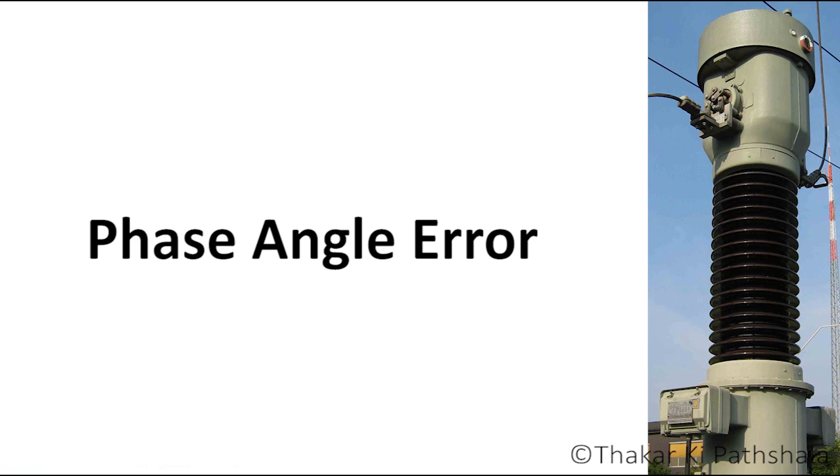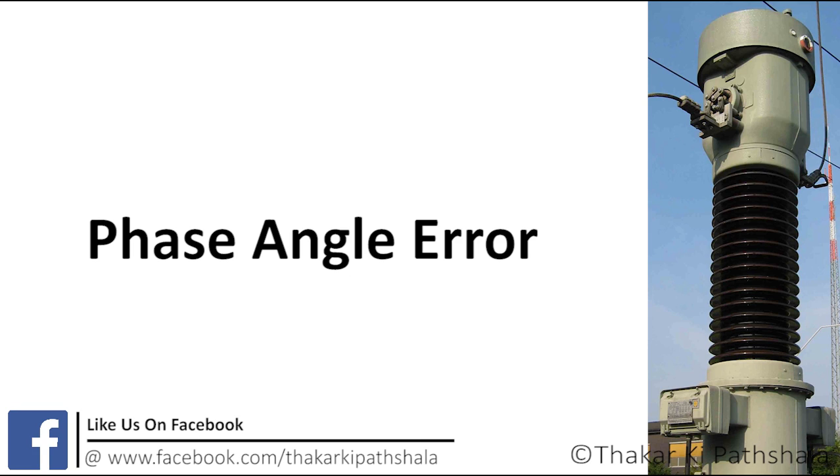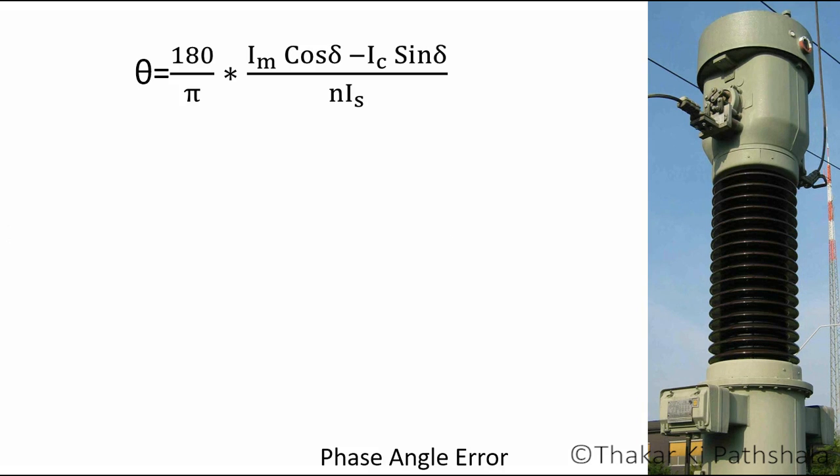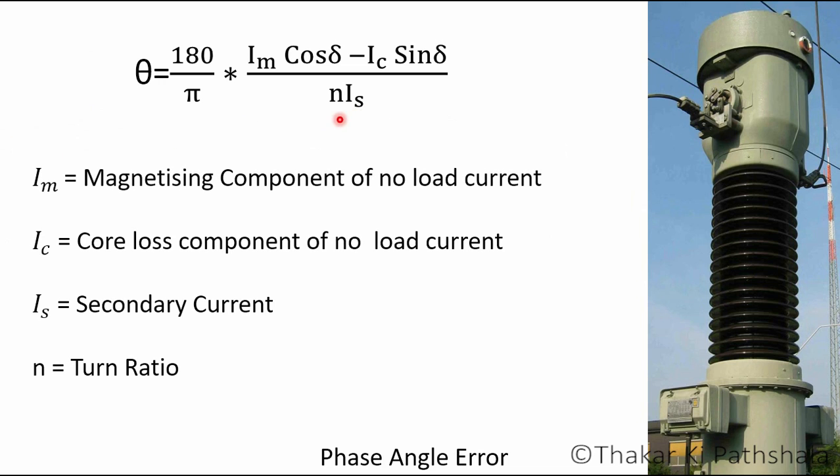So error occurs in measurement, which is called as phase angle error or phase error in current transformer, and it is denoted by theta. Equation to find this error is like this: theta is equal to 180 upon pi times Im cos delta minus Ic sine delta divided by N into Is. Here Im is magnetizing component of no load current, Ic is core loss component of no load current, Is is secondary side current. N is called as turn ratio for transformer.